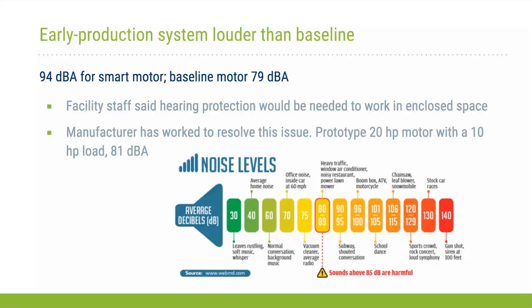The 10 horsepower smart motor that was tested at San Ysidro was a pre-production model, and it was noted that it was significantly louder than the existing premium efficiency induction motor. So 94 dB A-weighted for the smart motor versus 79 dB A-weighted for the baseline motor.